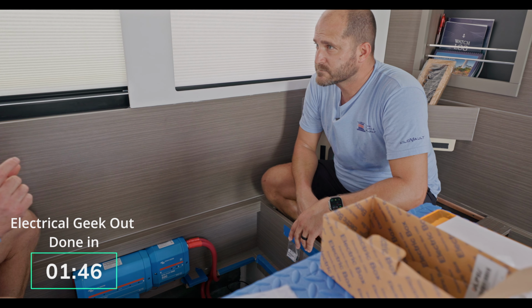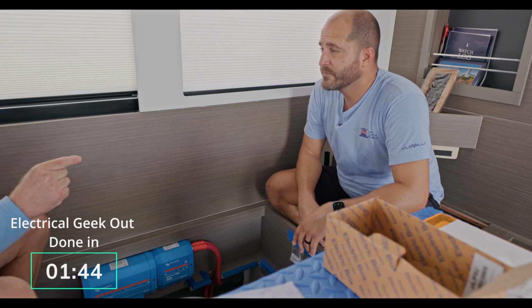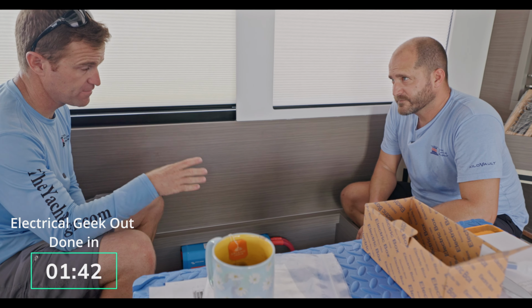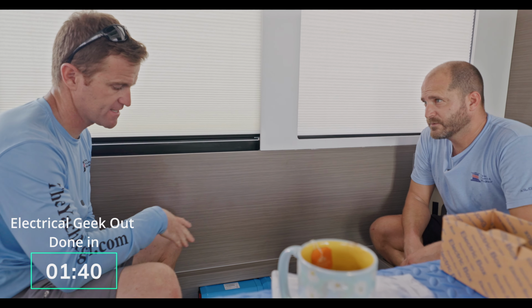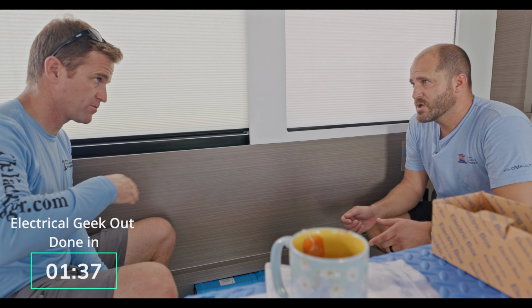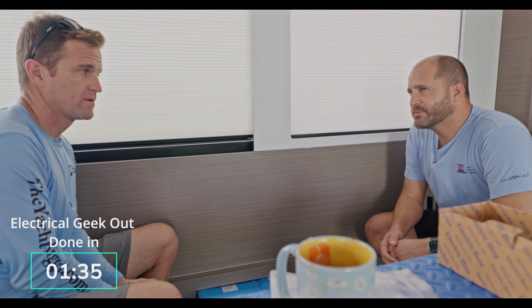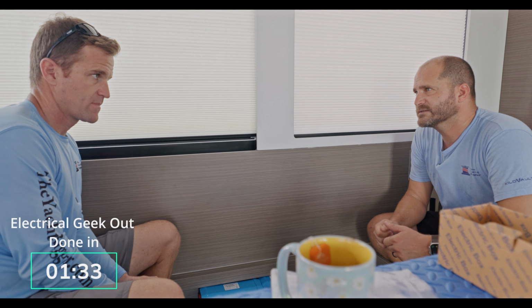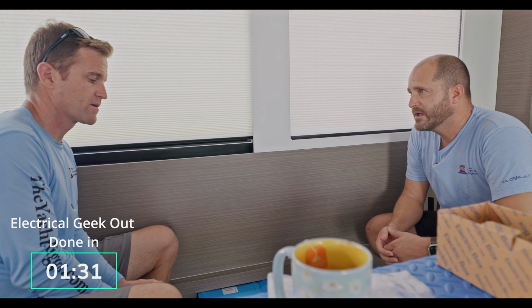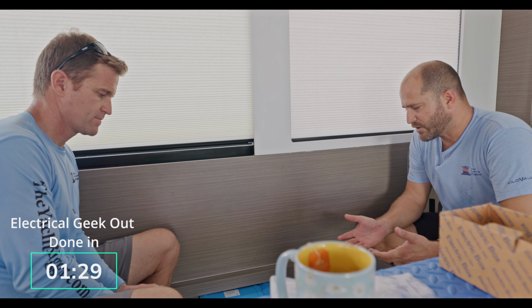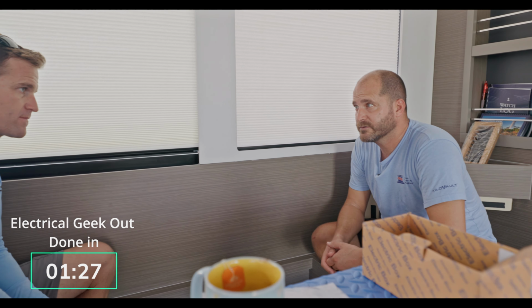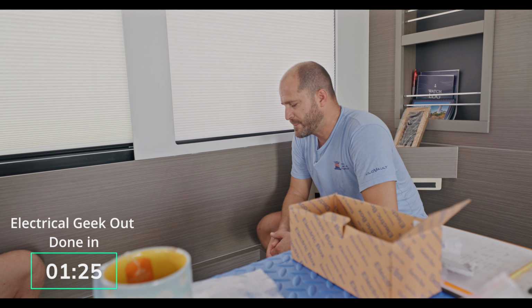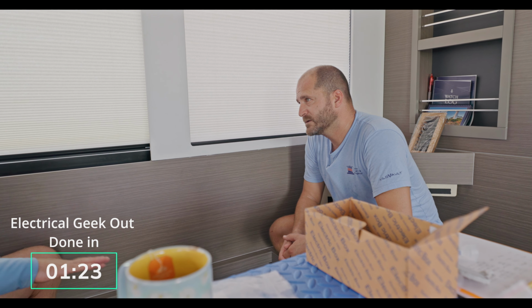The Class T fuses are specifically to protect the cable, the wire, from overload from the battery bank. So if there's an excessive draw from the inverter or anywhere in the system, yes, but most likely just a dead short, because a dead short will cause fire. The dead short could occur in the inverter.